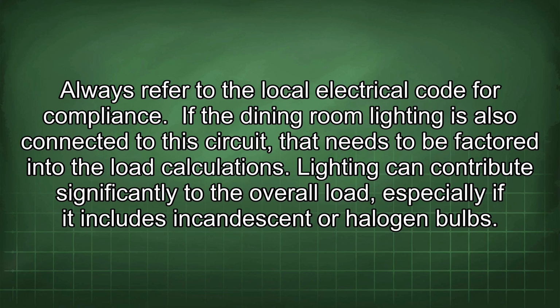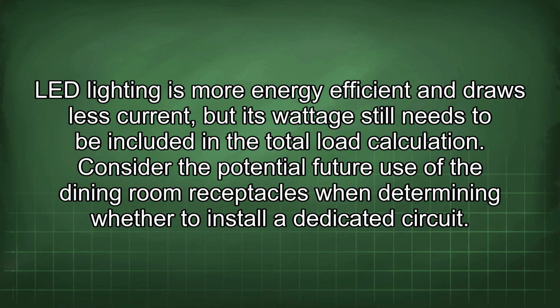If the dining room lighting is also connected to the circuit, that needs to be factored into the load calculations. Lighting can contribute significantly to the overall load, especially if it includes incandescent or halogen bulbs. LED lighting is more energy efficient and draws less current, but its wattage still needs to be included in the total load calculation.